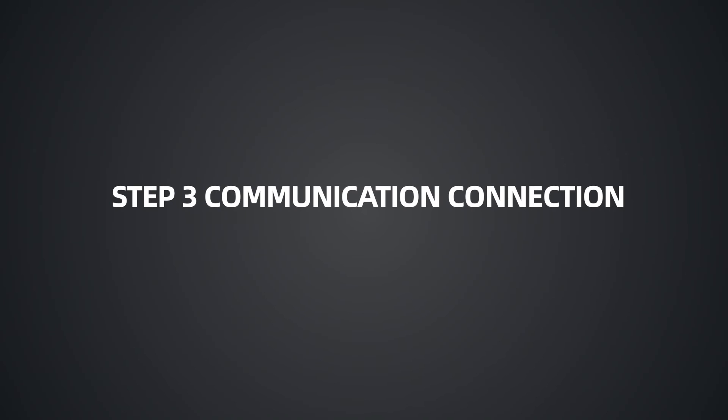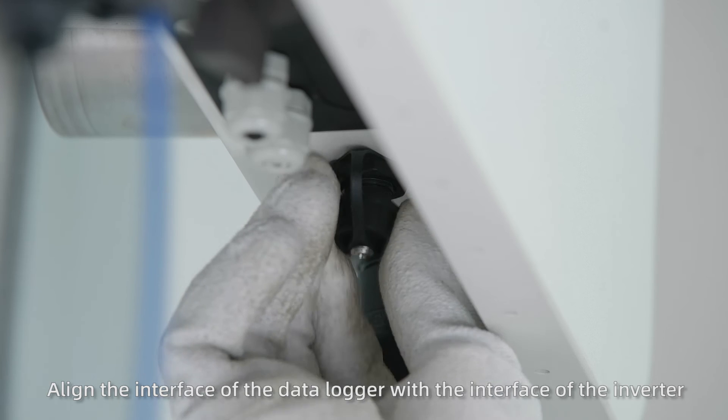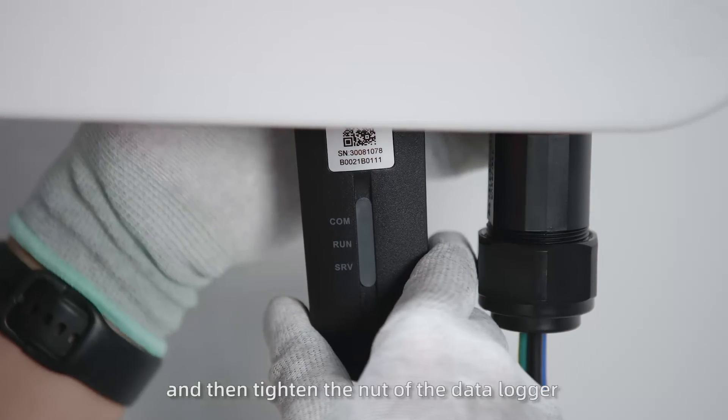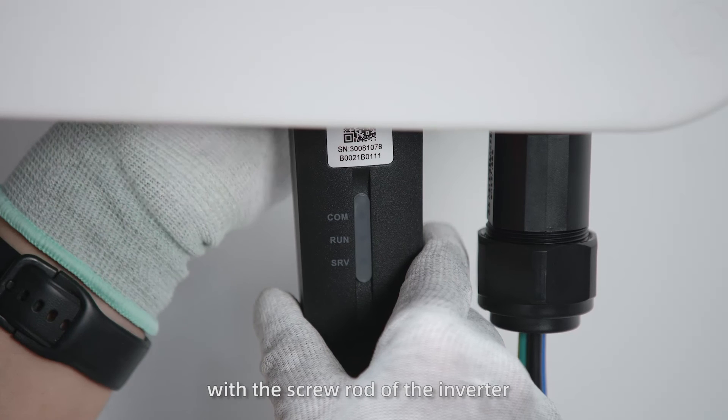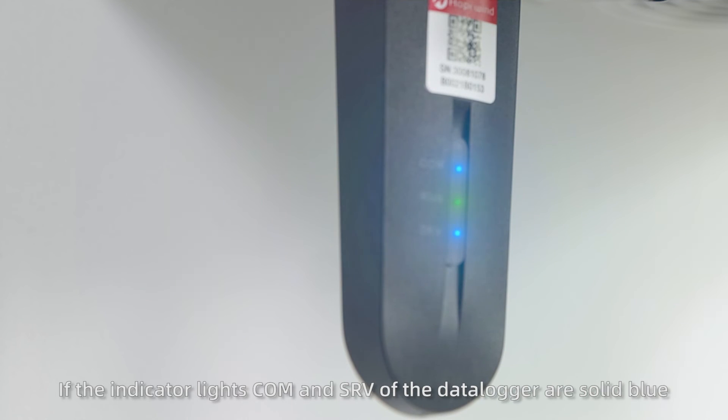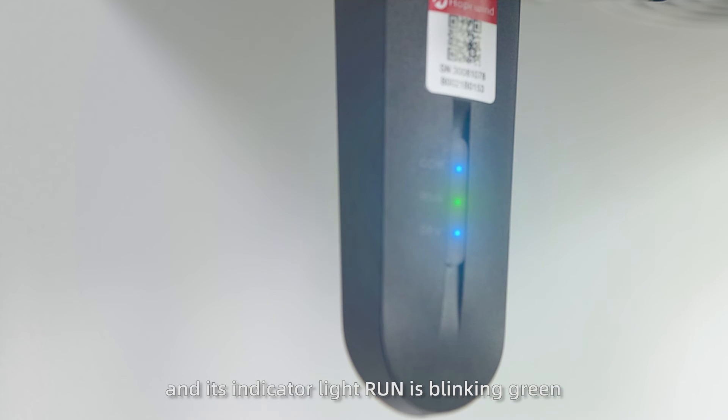Step 3 Communication Connection. Align the interface of the data logger with the interface of the inverter, insert it tightly, and then tighten the nut of the data logger with the screw rod of the inverter. When the inverter starts up, if the indicator lights COM and SRV are solid blue, and the run light is blinking green, the data logger is in normal operation.